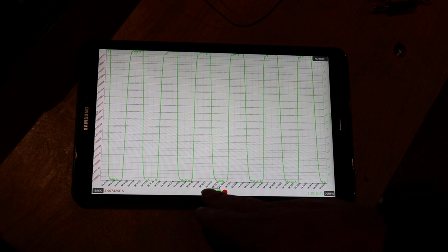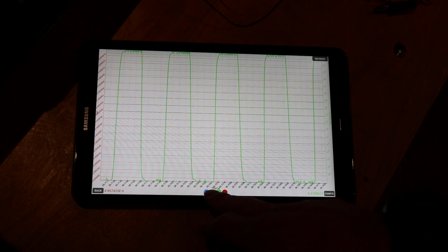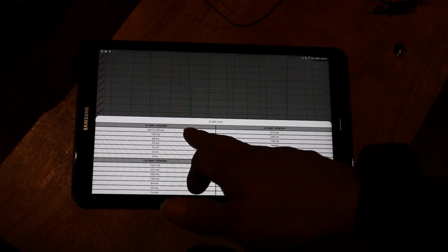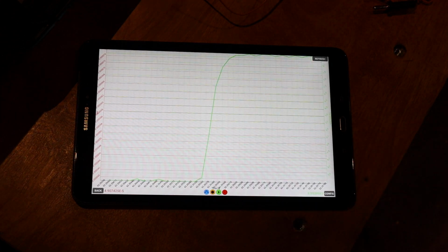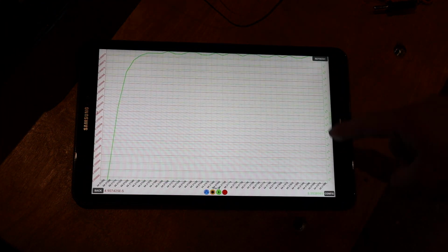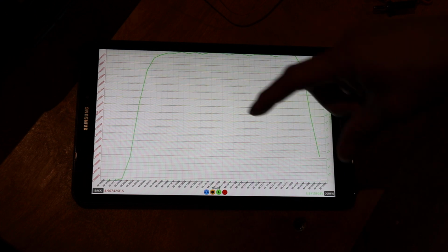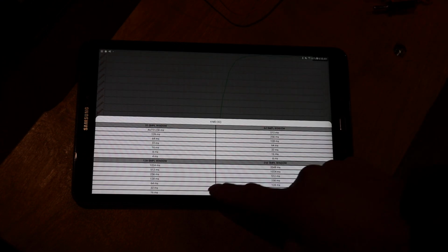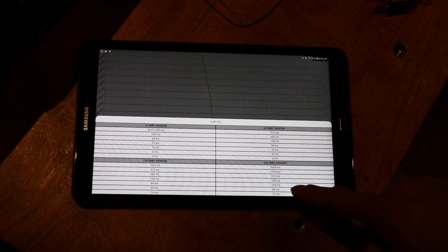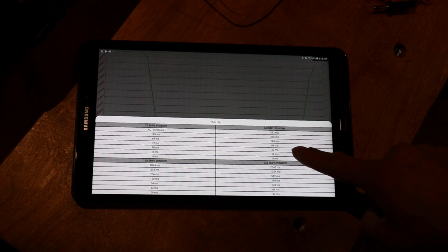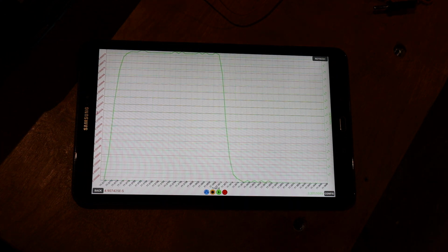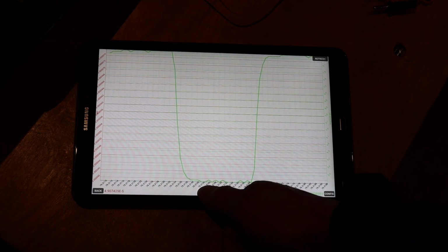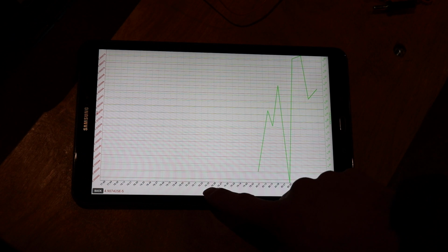Now I'm gonna go back to the speed, make this a lot faster, but it's going to be a smaller measurement window. So for example, we can take 4 millisecond data points, but notice we're only looking at certain parts of this signal. So that's what I was trying to get at earlier. Now we can get a bigger picture, go out to 8 millisecond data points. You know, it's going to give us a little bit more. That's about one of those waves.